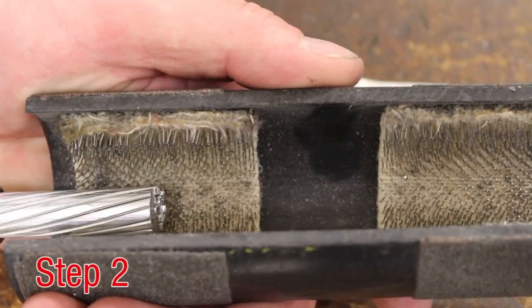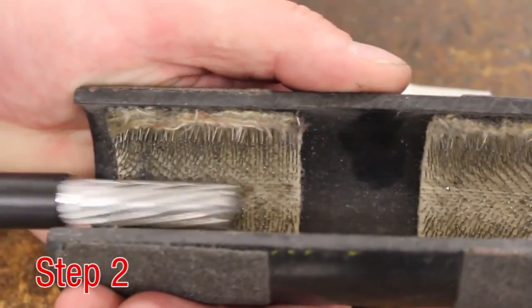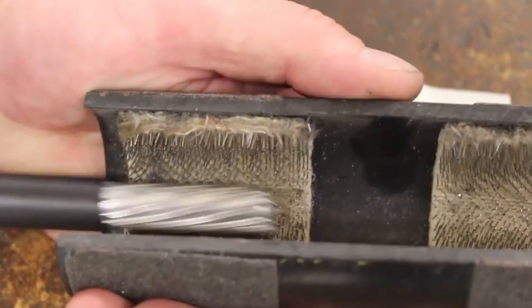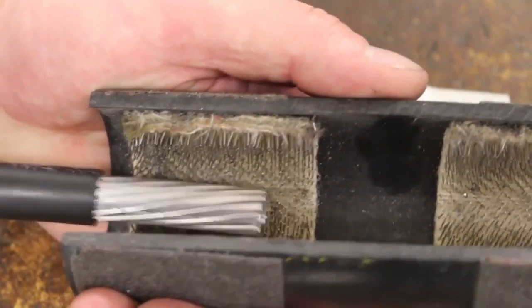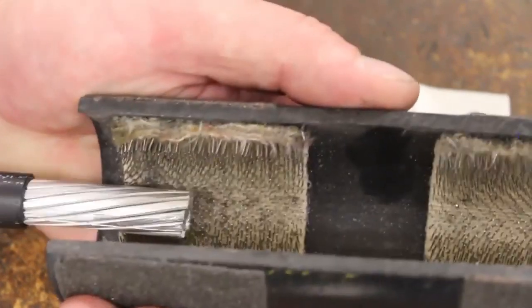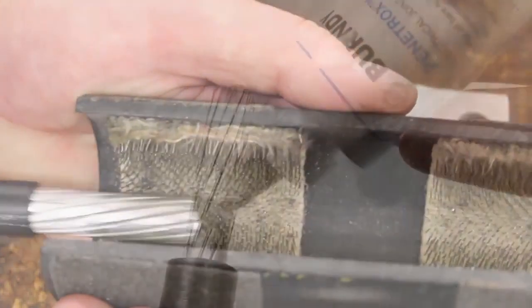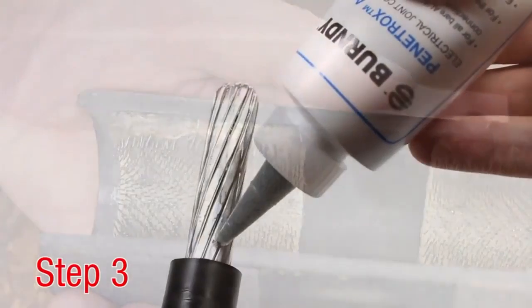Step 2. Scratch brush conductor thoroughly. Aluminum oxidizes very quickly and forms a hard, non-visible, non-conductive coating that develops on the surface. It is very important to always wire brush the stripped portion of the wire before making the connections.